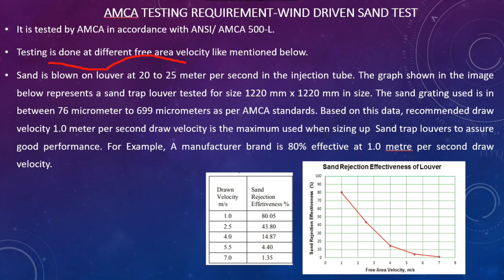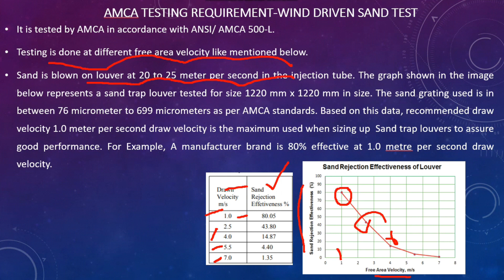The testing is done at different free area velocities: 1 m/s, 2.5 m/s, 4 m/s, 5.5 m/s, and 7 m/s. Based on the draw velocity, the sand rejection effectiveness is plotted on a graph — X-axis is free area velocity and Y-axis is sand rejection effectiveness. For example, at 1 m/s you can see how much sand rejection effectiveness is achieved, and similarly at 2.5, 4, and 5.5 m/s. The sand is blown onto the louver at 20 to 25 m/s in the injection setup.